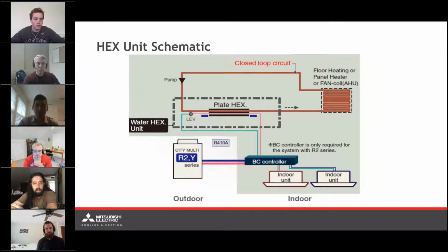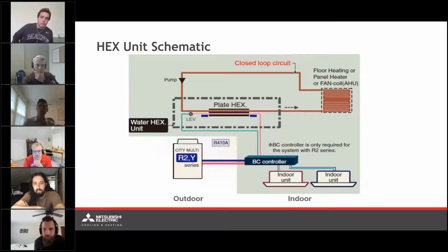Now, I have drawn up a schematic for how exactly a HEX unit would play into a VRF system. For this particular layout, I'm just going to start with the outdoor unit and work my way in. So this looks like a typical heat recovery VRF system. We have the outdoor unit, which is going to be an R2 series, connected to a BC controller, 2 pipes going in. On the BC controller, we have 2 cassettes attached to this. Each cassette is in its own independent mode, so one of these cassettes is going to be heating, the other in cooling. But in addition, we're also going to have this water HEX unit. And again, the HEX is just registered on the system as just another indoor unit, so no additional programming needs to be taken into account. Once it's plugged in, the system knows what it's looking at here. It's just another fan coil, for lack of a better term, or another indoor unit on the system as a whole.